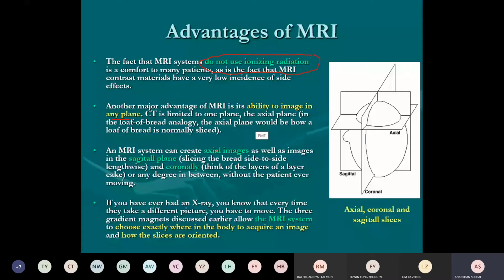An MRI system can create images in any view. Okay. Difficult for CT scan. CT scan, you can't do that. One slice only, one plane only. Okay. If you ever had an X-ray, you know that every time they take a different picture, you have to move. The three gradient magnets discussed earlier allow the MRI system to choose exactly where in the body to acquire the image and how the slices are orientated. Yeah, the slice orientation is done by the gradient magnets.